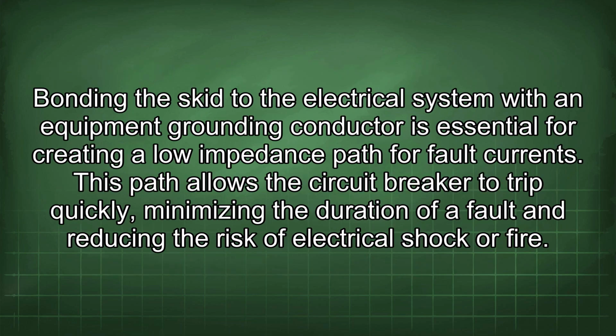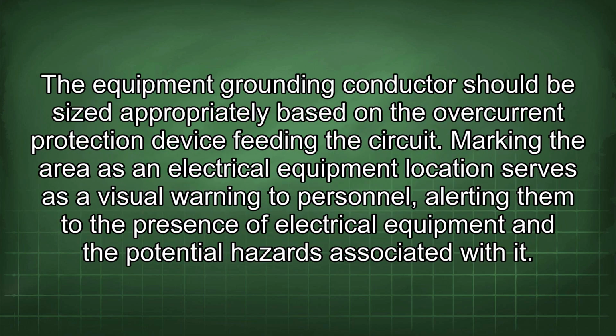Bonding the skid to the electrical system with an equipment grounding conductor is essential for creating a low impedance path for fault currents. This path allows the circuit breaker to trip quickly, minimizing the duration of a fault and reducing the risk of electrical shock or a fire. The equipment grounding conductor should be sized appropriately based on the overcurrent protection device feeding the circuit.